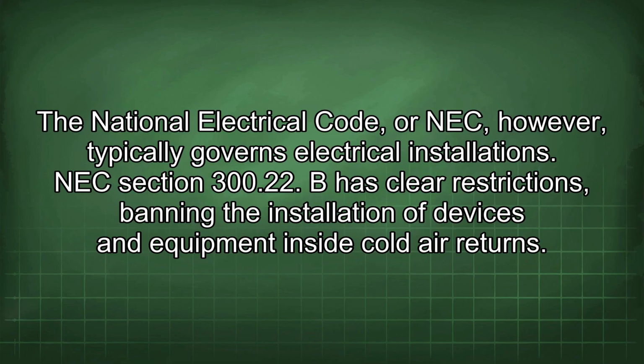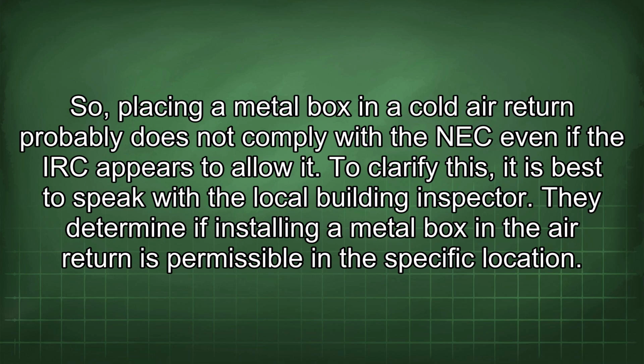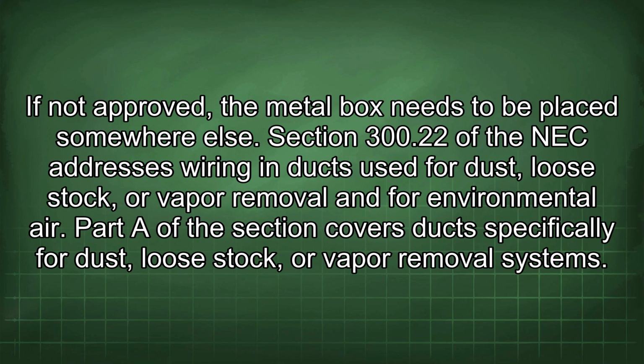The National Electrical Code, or NEC, however, typically governs electrical installations. NEC Section 300.22(B) has clear restrictions banning the installation of devices and equipment inside cold air returns. So, placing a metal box in a cold air return probably does not comply with the NEC even if the IRC appears to allow it. To clarify this, it is best to speak with the local building inspector. They determine if installing a metal box in the air return is permissible in the specific location. If not approved, the metal box needs to be placed somewhere else.